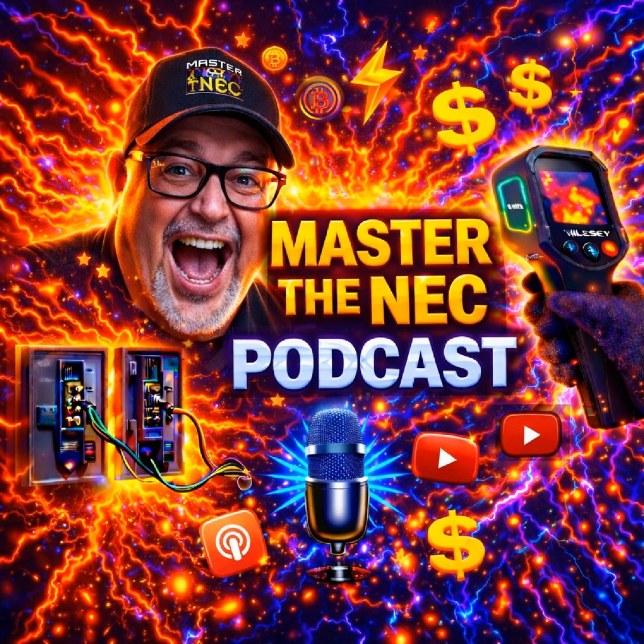So if you remember one thing from this episode, and we've been an hour and 30 minutes approximately, if you remember only one thing from this podcast, remember this. A GFCI isn't really asking, is current going to ground? It's asking, did all the current that left through my monitored conductors return through my monitored conductors? If yes, the GFCI sees a balance. If not, it sees differential current. Once you understand that, suddenly all of these issues start to make sense.